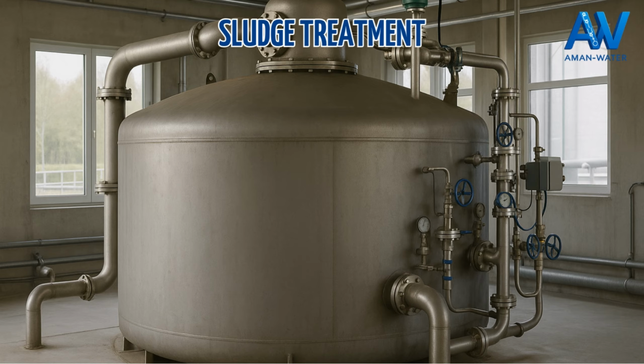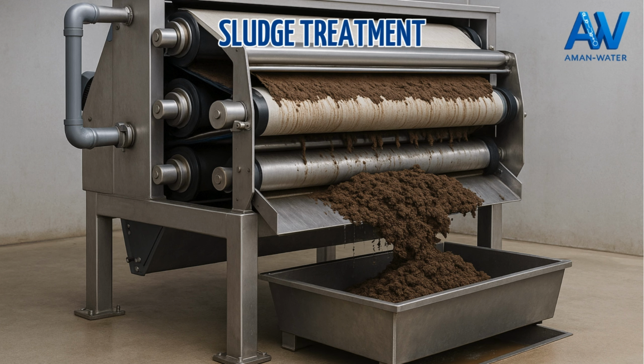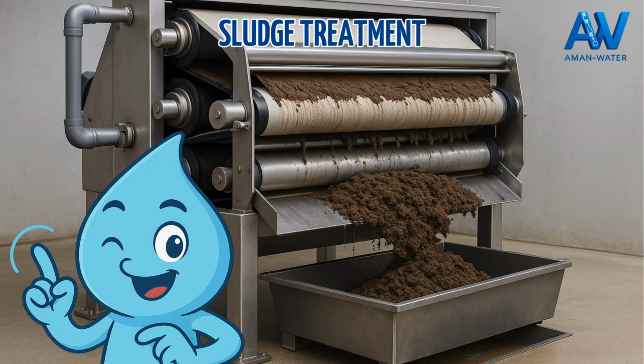This biogas can be used to produce heat or electricity. In some modern treatment plants, the energy generated by digestion covers a large part of internal needs, reducing the consumption of fossil energy. After stabilization, the sludge is dewatered. This step aims to remove the water still trapped within the structure of the sludge. Centrifuges, filter presses, or drying beds are used for this purpose. The dry solids content can then reach 20 to 30%, which greatly facilitates storage and transport. At this stage, the material obtained is compact and much easier to handle.